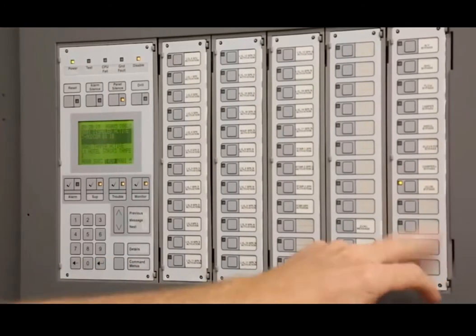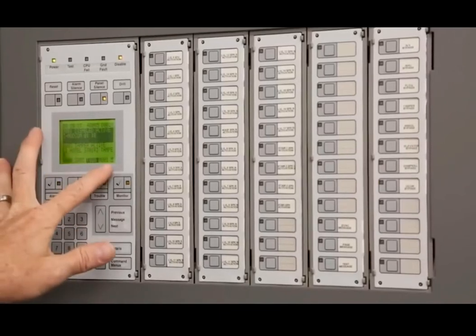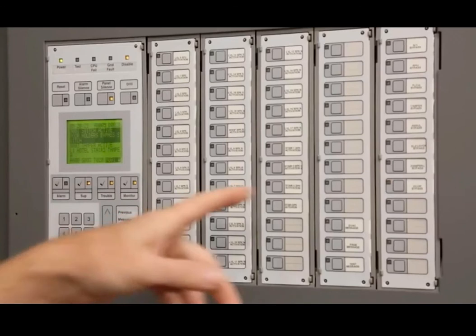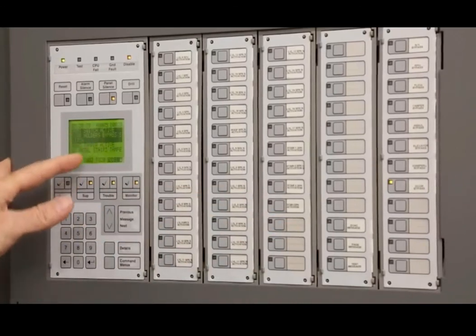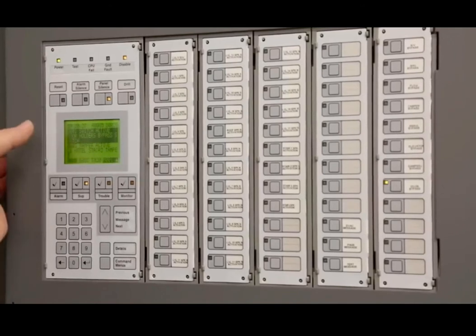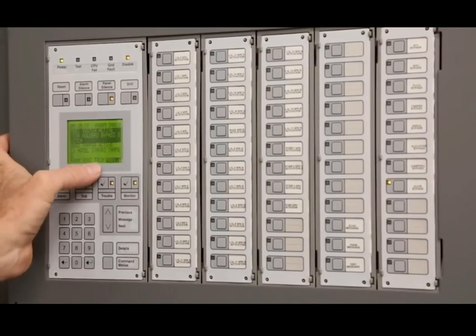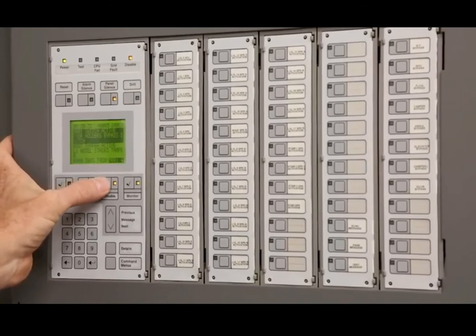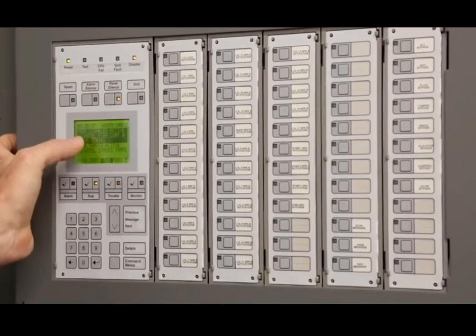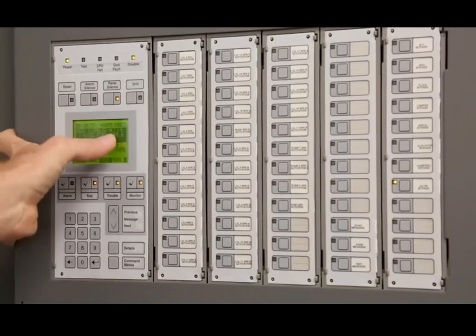For instance, like I said, right now we hit door bypass. If you notice, we got monitor point active. If you want to know what it is, just hit monitor points, and it'll be more descriptive. It'll say right here that the switch is active, door holder switch. So basically it's saying that the doors are bypassed. If you notice, the troubles went from 1 to 20 now, and we can scroll through them, go up or down arrow. Highest right there is 20, and they're all disable active.